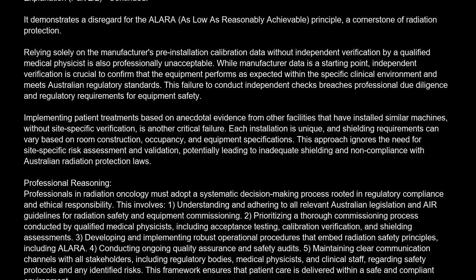Implementing patient treatments based on anecdotal evidence from other facilities that have installed similar machines, without site-specific verification, is another critical failure. Each installation is unique, and shielding requirements can vary based on room construction, occupancy, and equipment specifications. This approach ignores the need for site-specific risk assessment and validation, potentially leading to inadequate shielding and non-compliance with Australian radiation protection laws. Professional reasoning.